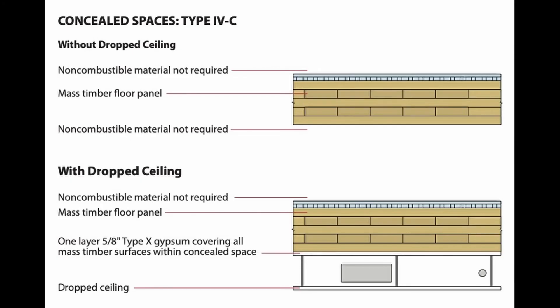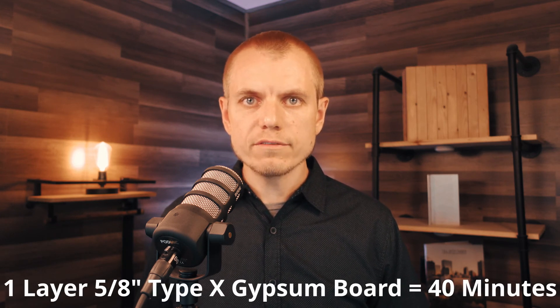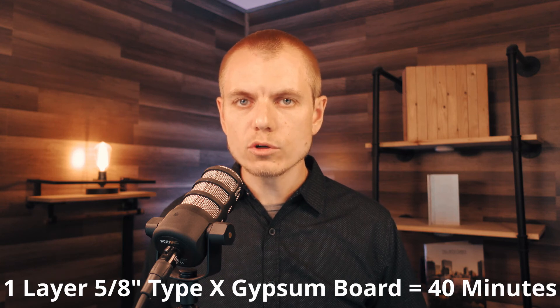Type 4C is very similar to Type 4HT with one key exception: we don't have the option to leave mass timber exposed within the concealed space. Unlike 4HT — where you could leave the timber exposed but sprinkler the area or fill with non-combustible insulation — in a 4C building we must always cover the mass timber within the concealed space. The code requires a non-combustible material providing a minimum 40 minutes of fire resistance; a single layer of 5/8" Type X gypsum wallboard accomplishes this.